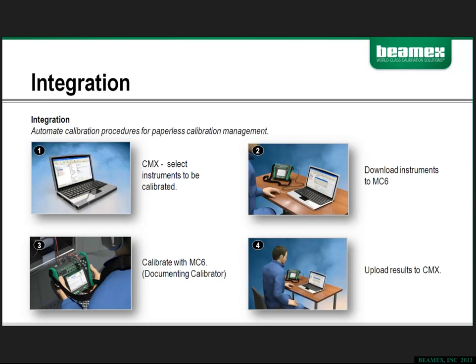And a lot of calibrations are fully automated, say for a temperature transmitter or something like that. And you would hit the start button, and it will run through the process, record all of the data, and let you know at the end whether or not that particular instrument passed or failed. At which point, if it passed, you could complete your calibrations for the day, come back into the shop, reconnect the MC6 to your computer, and upload all of that data directly back into the CMX software. At that point, it becomes a static record that is updated. It updates that particular tag or position within the system, and it keeps it current until the next time it's due for calibration.